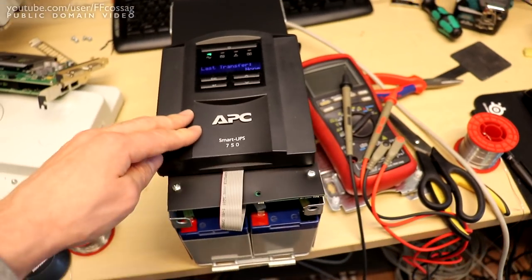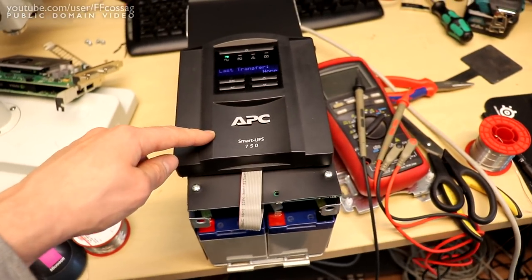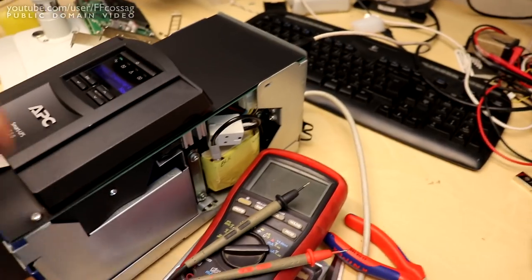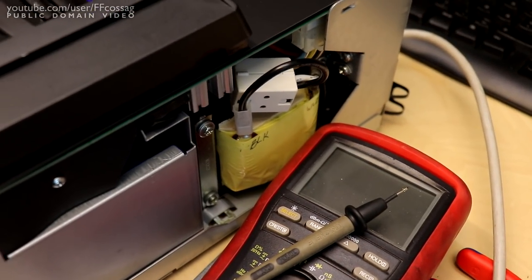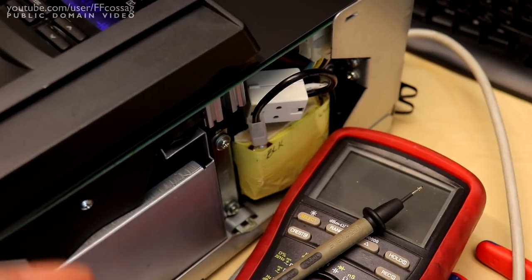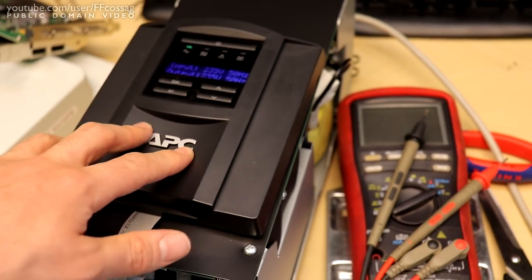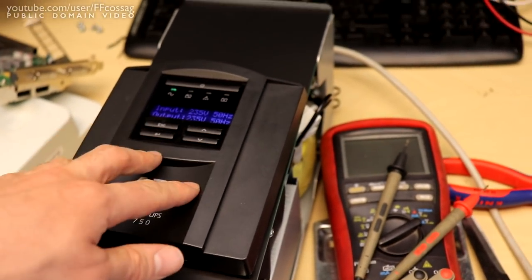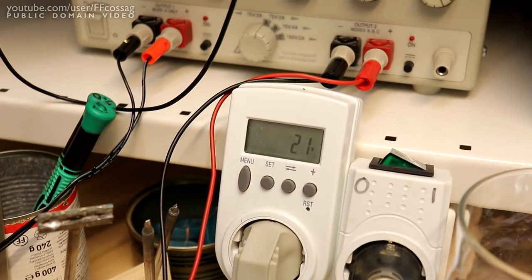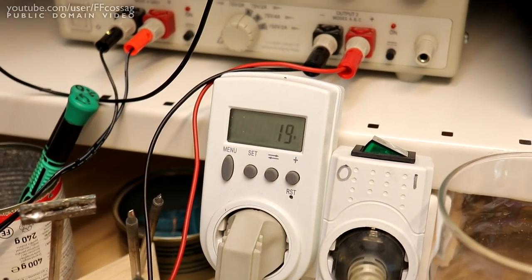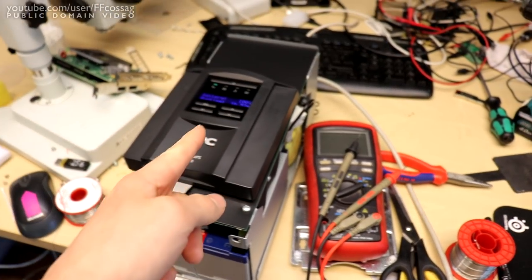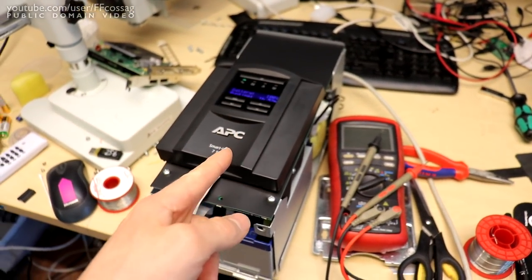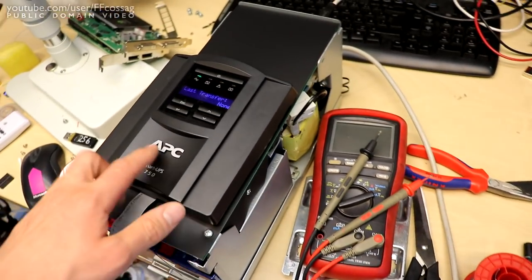An issue with these smart UPS models, even the small ones, is that the transformer, the big one over there, will be connected to the mains at all times no matter what. That draws about 20 to 25 watts of power. In line interactive mode right now, we're drawing 21 watts just sitting idle. This UPS with nothing else connected is drawing as much as an entire server of mine, and that's not good.